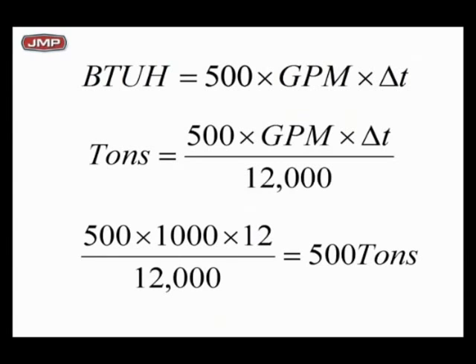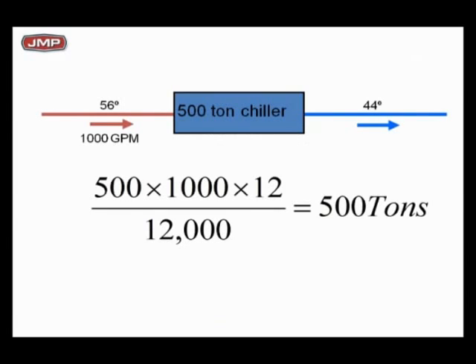Are we going to change the flow rate? What happens to the delta T? That's the thing I want to ask you. So let's take a look at this. Here's my 500 ton chiller. You designed it for 1,000 GPM at 56 degree return and 44 supply.